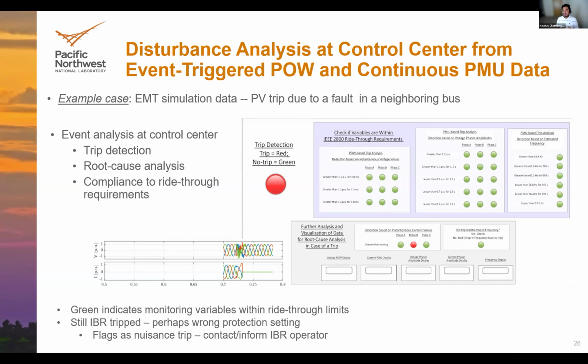So which kind of flags that, okay, this was a nuisance trip. So the IBR was not supposed to trip, but it still tripped. This helps the operator inform the manufacturer or someone else operating the plant that something might be wrong with your relay setting. So you probably need to go back and check or retune it to match the ride-through requirements. In this particular case, it was a transient overcurrent in one of the phases, which was not accommodated as per the ride-through requirements.